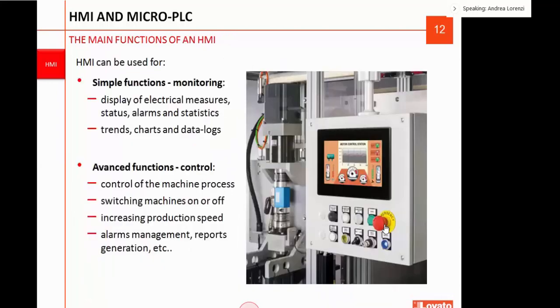HMI can be interfaced with digital metering devices, controllers like power factor controllers, automatic transfer switch controllers, motor starters like soft starters and drives, or external gateways, softwares, and SCADA. If you need to interface the HMI to a monitoring system like software or SCADA, you can connect the HMI to the local area network and create interaction between all these devices. HMI can be used to perform simple or advanced functions. Simple functions include using the display to read electrical measures, machine status, alarms, statistics, live trends, data logging, and charts. Advanced functions include commanding the machine process, switching on or off, increasing production speed, managing alarms, and generating automatic reports.